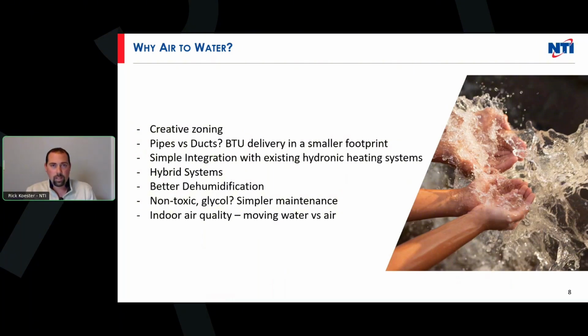Whereas with a refrigerant-based system or an air-driven one, like a heat pump, you're dealing with a lot of refrigerant guidelines. If you had a leak in a system, you had to make repairs in the system. There's recovery, there's actually fixing it, then pressure testing and evacuating the system. It's a lot of time and money to sit there on a job and do it. And most people are not doing it right because they know how expensive it is to do.